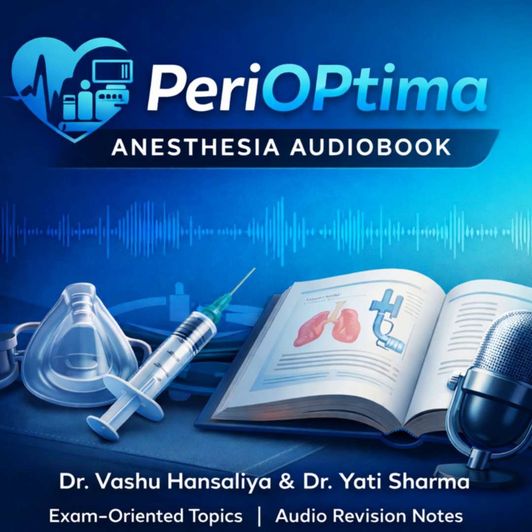Moving on to vaporizers. The outline calls this exam core. It is. The purpose of a vaporizer is to turn a potent liquid anesthetic into a precise vapor concentration. We primarily use what are called variable bypass vaporizers. How does that work, simply? You have your fresh gas flow coming from the flowmeters. The vaporizer splits this stream. One part goes straight through a channel, that's the bypass. The other part is diverted down into a chamber that contains the liquid anesthetic, like Sevoflurane or Isoflurane. And it picks up the vapor there.